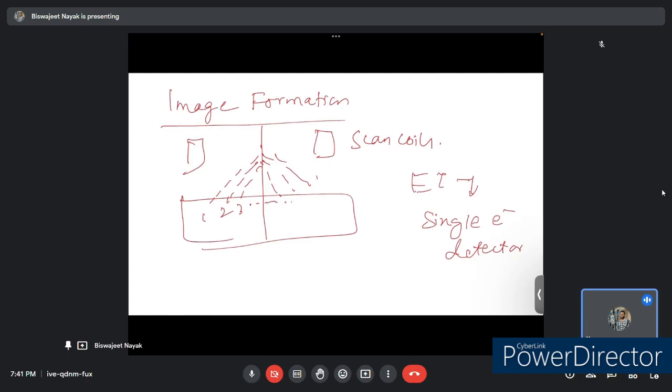It is also possible to measure the output from more than one detector simultaneously. When that is done, multiple grayscale SEM images are built up at the same time during the scan. It is essential to realize that even when these multiple signals are being collected simultaneously and multiple images are produced, only one scan is needed.